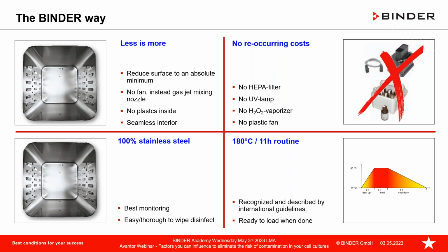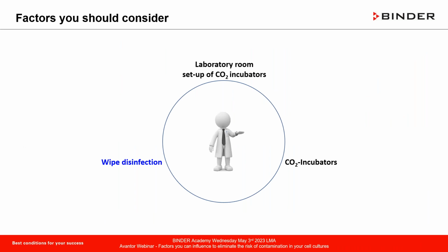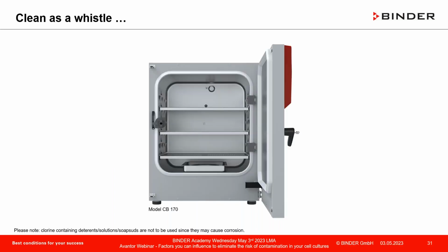Wonderful for your contribution. All right, then, let's proceed on to the last topic, wipe disinfection. Very common questions we received from our users in cell and tissue cultures. Right here, we're taking a look at an opened CO2 incubator. Please note, in general, chlorine-containing detergents, solutions, soap suds are not to be used since they may cause corrosion. And that is not good for the reliability of a continuous operation over many, many years.